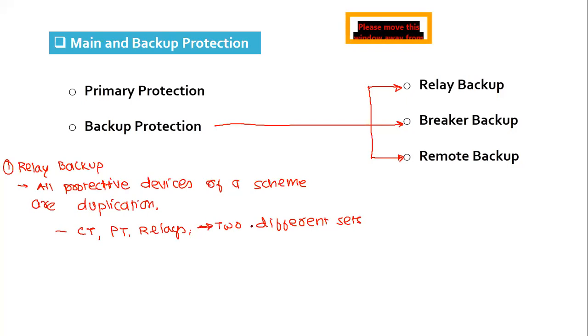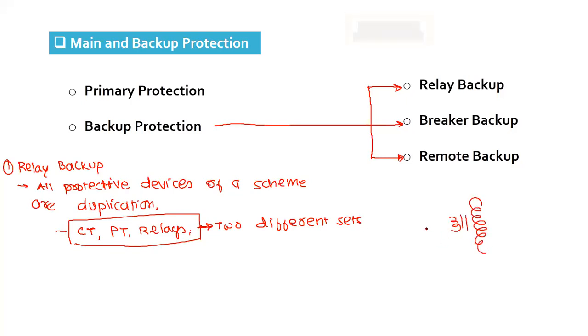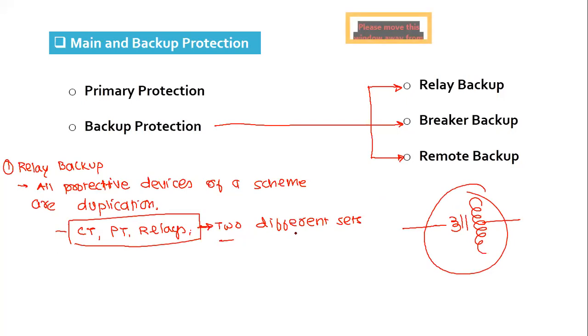Both will act as main protection 1 and main protection 2. Understood? Suppose this is a transformer, and I want to give it a backup protection, differential protection. So what do we do? We have two different sets for the same transformer - two CTs, two relays, everything is doubled. They are exactly identical.